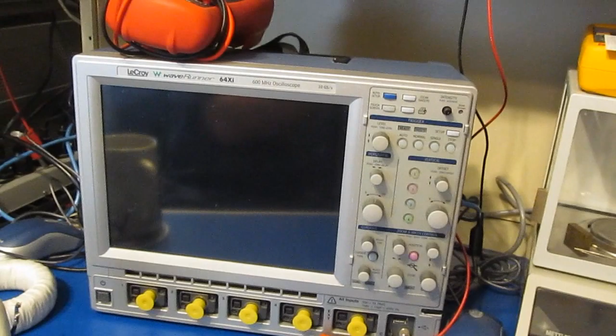Now on newer oscilloscopes, like this LeCroy 64XI, this has the interleaving mode built into it. So this scope will normally capture at 5 gigasamples per second, and that's on all 4 channels. This scope has hardware to interleave the first 2 and the last 2 channels. Basically what it allows you to do then is use channel 2 and 3 as your inputs and double the sample rate from 5 gigasamples to 10 gigasamples. My LeCroy Wavemaster does the same thing. That oscilloscope can capture at 10 gigasamples per second with all 4 channels, or it can do 20 gigasamples with 2 channels. Now again, these oscilloscopes also support RIS mode.